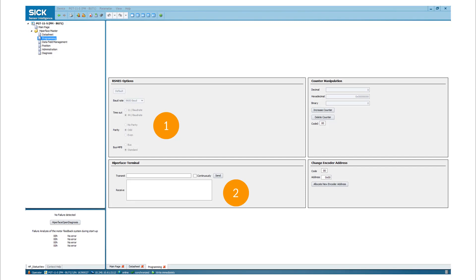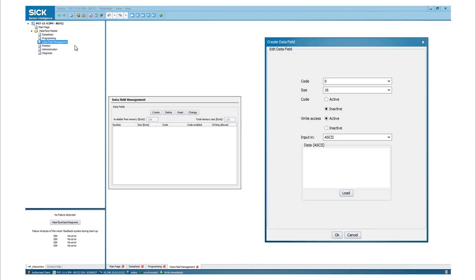If needed, you may also change the encoder address. By default, it is 40 hex. Data fields in a motor feedback system are also known as the electronic type label of a servo motor. With the function data field management, it is possible to store motor or application specific data.